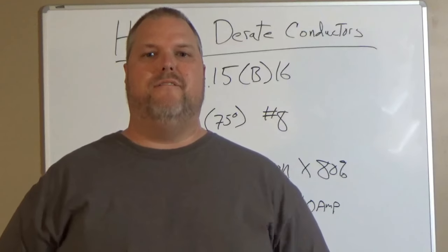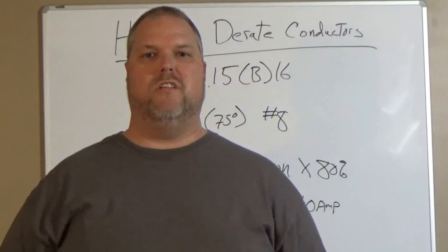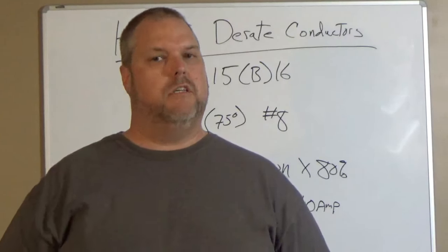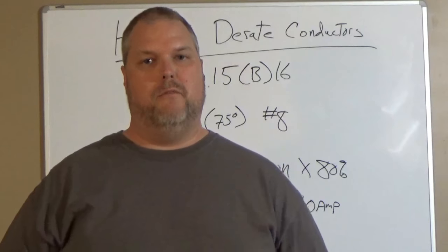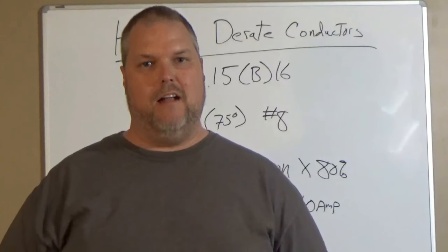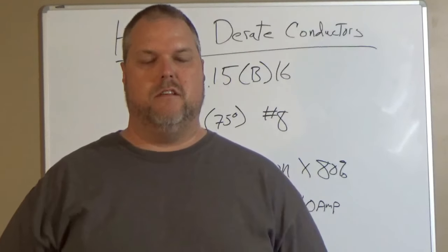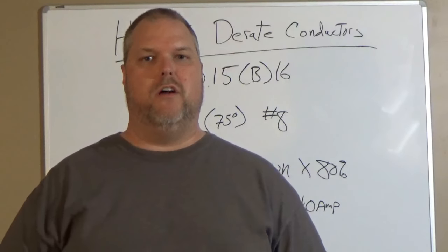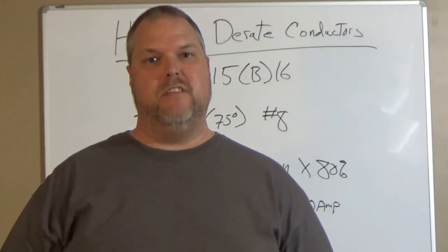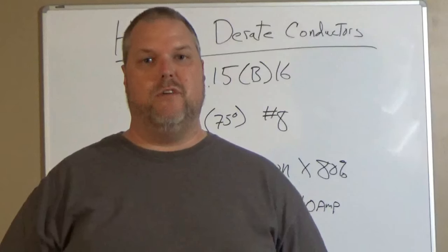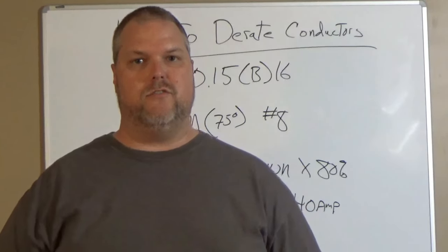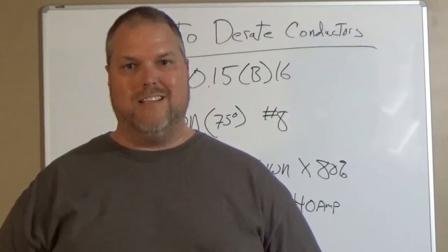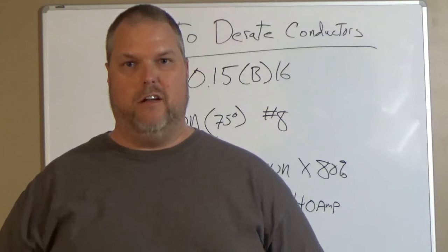Because remember, 50 is perfect world scenario—no load, it can hold up to a load of 50 amps. But remember, as we start filling that conduit up, it starts to take space. So we have to make sure that we understand: I have to derate after I get past three conductors. Remember, we're only talking about current-carrying conductors. The grounding conductor is not a current-carrying conductor.